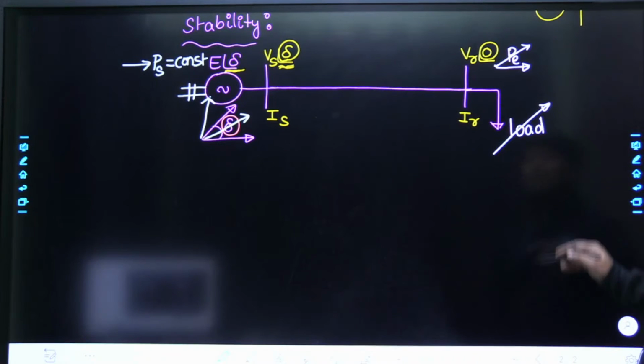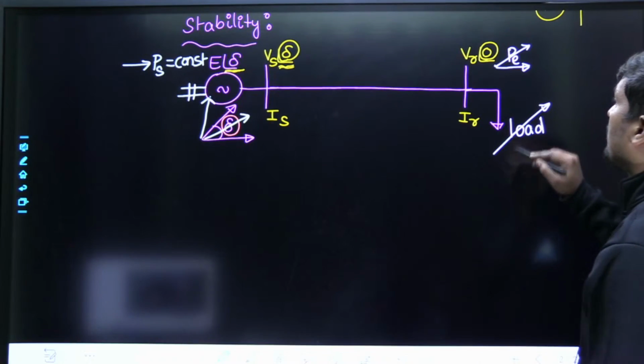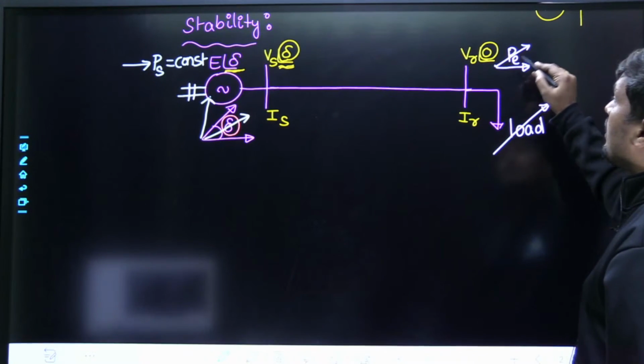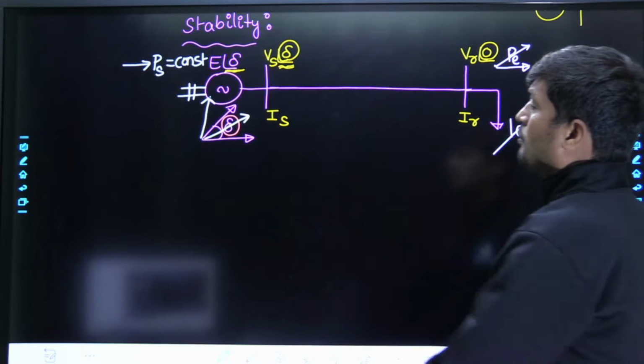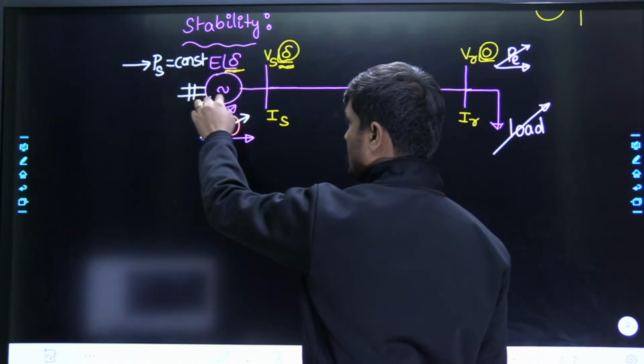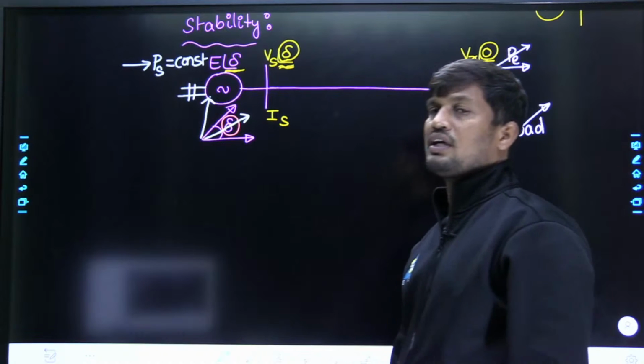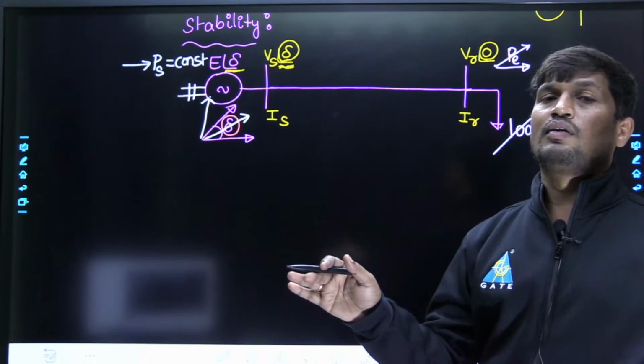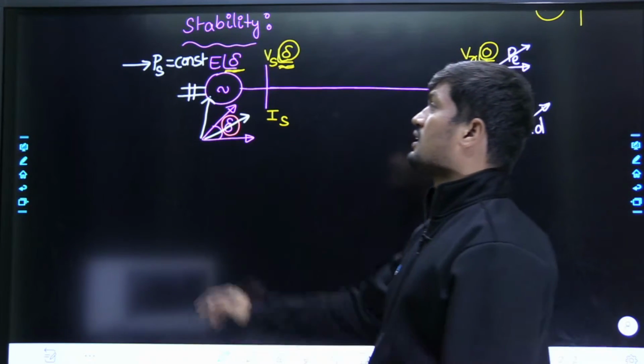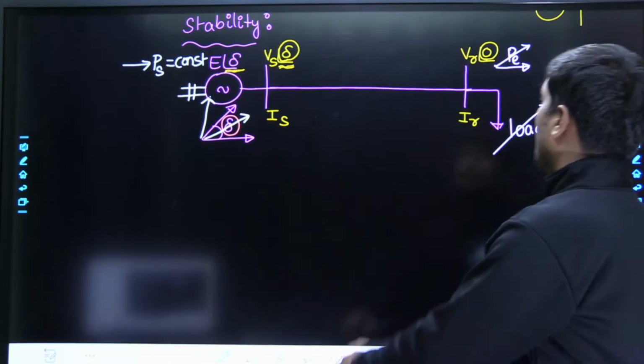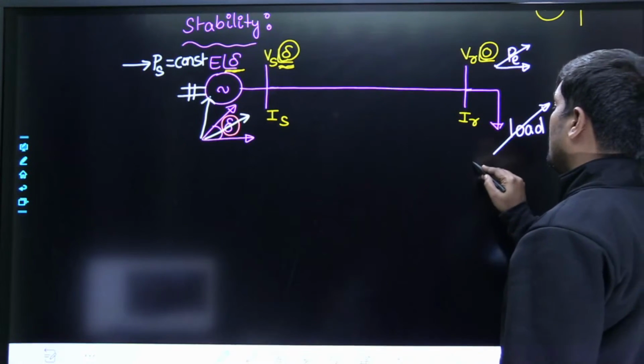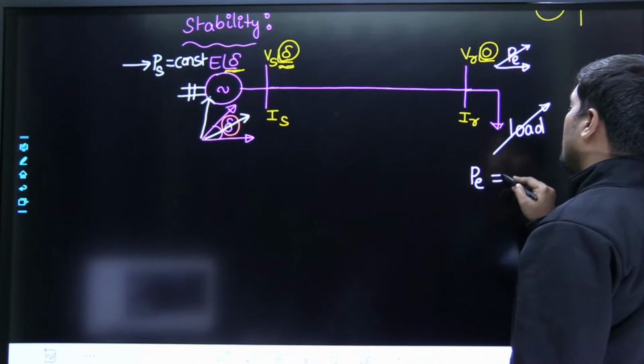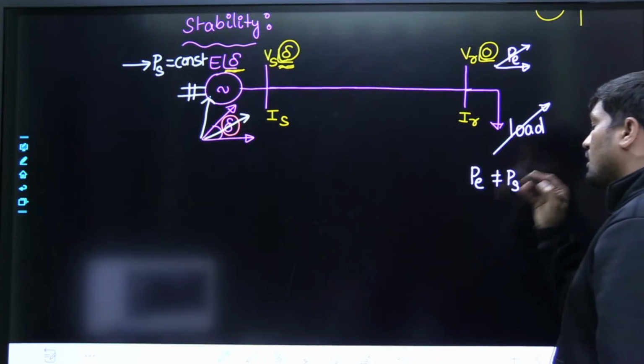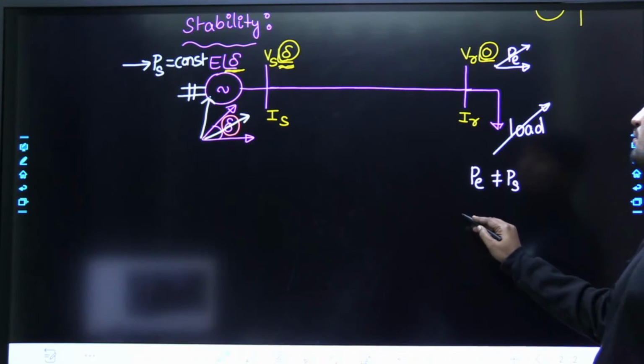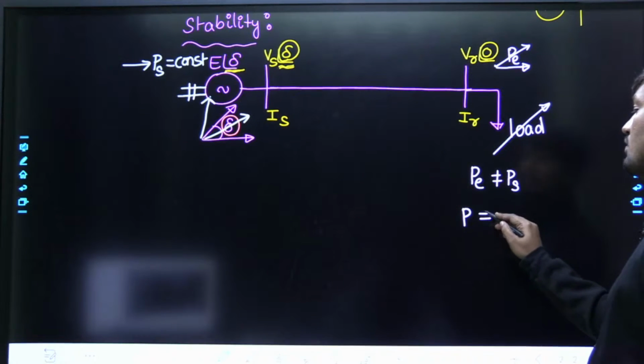When load varies at the load point, immediately electrical power at the load point also varies, but shaft power supplied to the synchronous generator with the help of the prime mover and speed governor will not allow the sudden change. Automatically shaft power remains constant and electrical power varies, so that electrical power is not equivalent to shaft power, and power losses is not equal to zero.